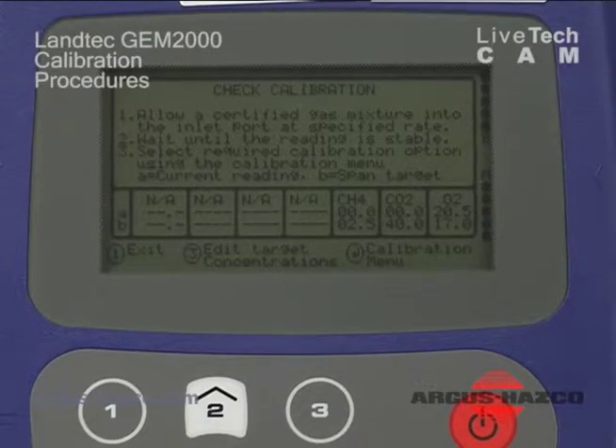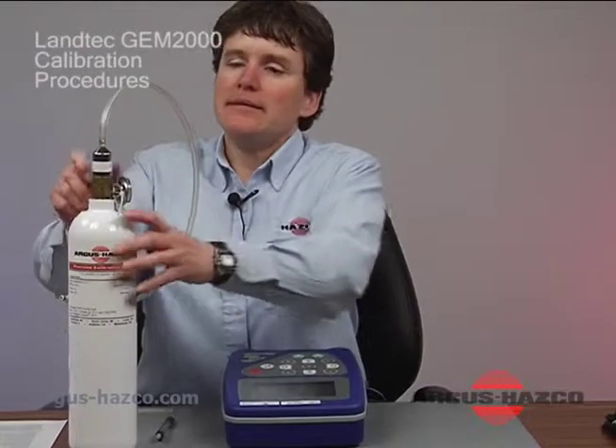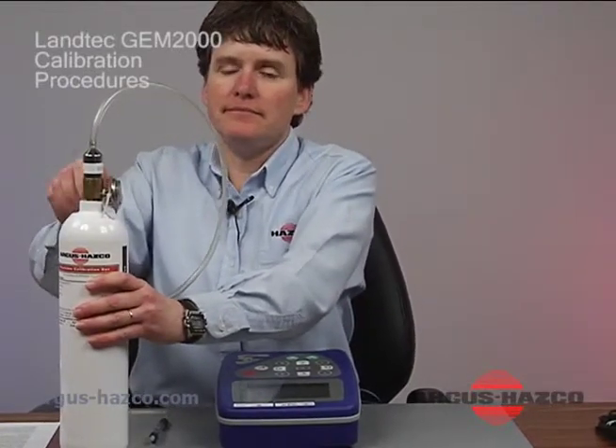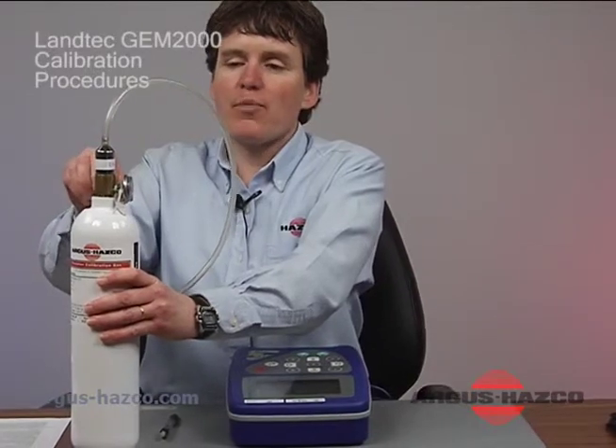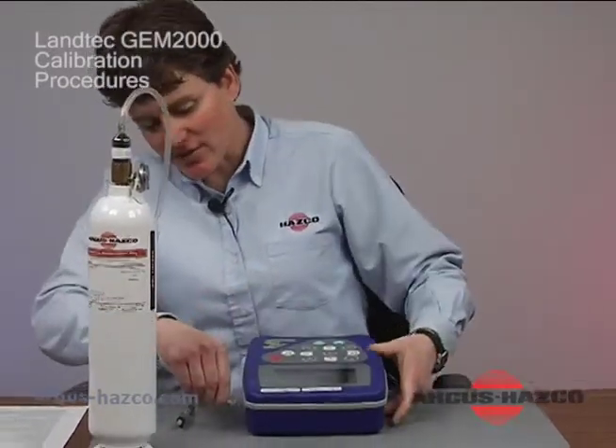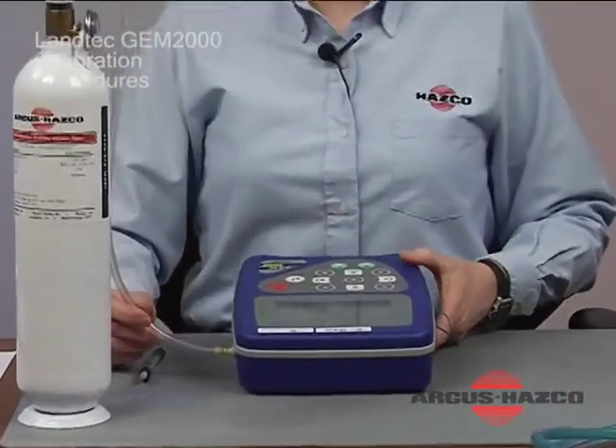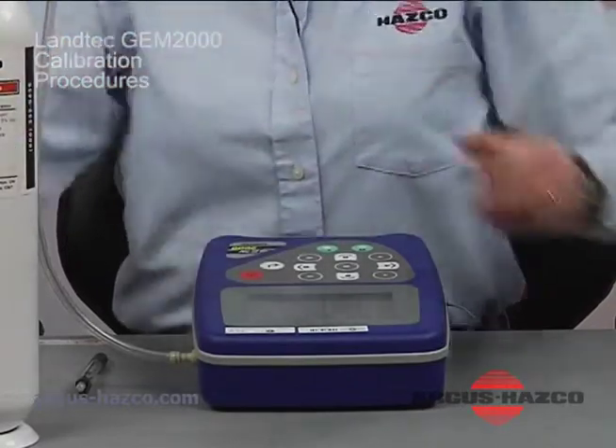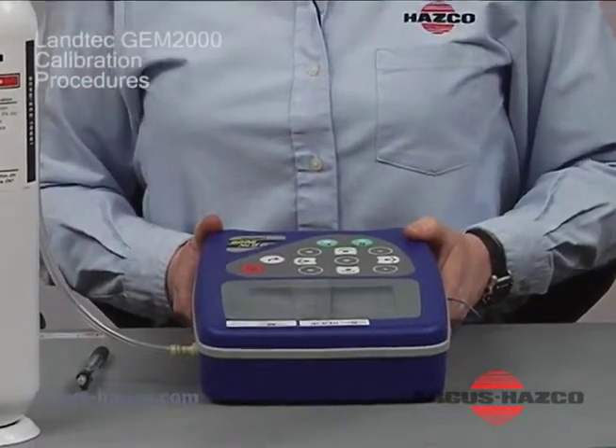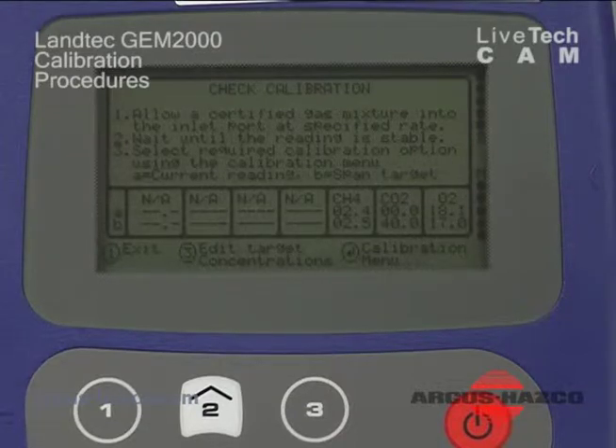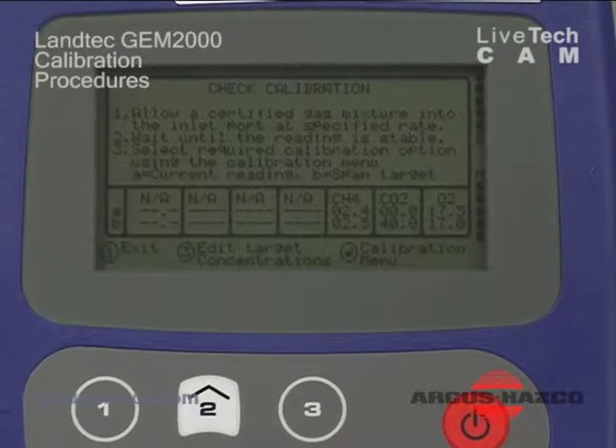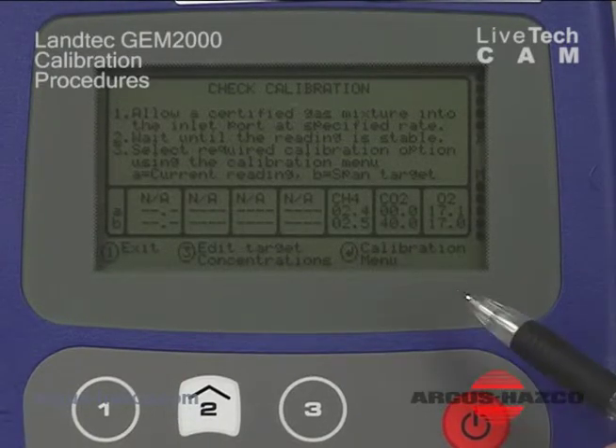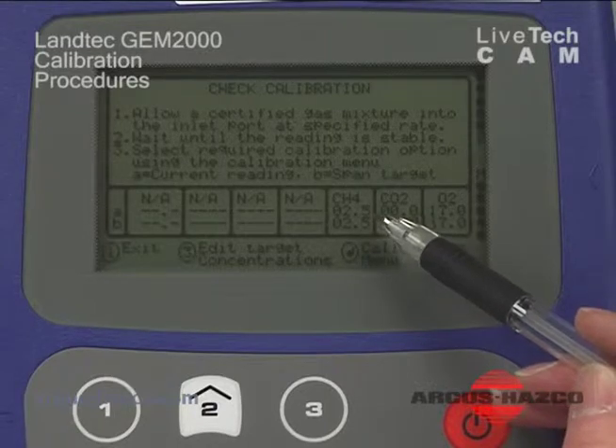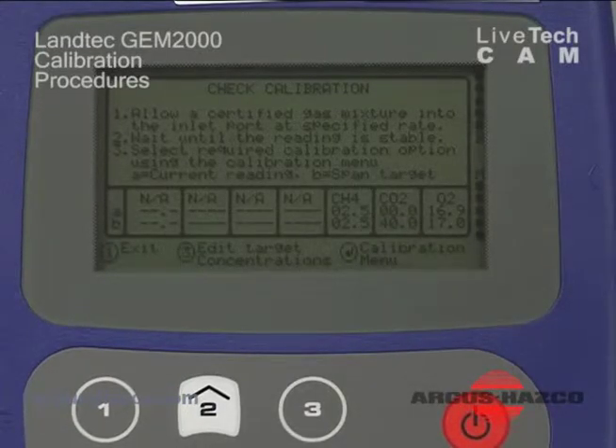So again, I want to go ahead and turn on my pump, turn on my regulator, and again I have a 0.5 liter per minute regulator attached to my calibration canister. Attach that to the inlet of my pump, let my gas flow. And again, you always want to wait 2 to 3 minutes to make sure you got good gas flow and good stable readings on your instrument. And if you look closely here, you can notice my 0 reading has increased to match the calibration value of my calibration cylinder.